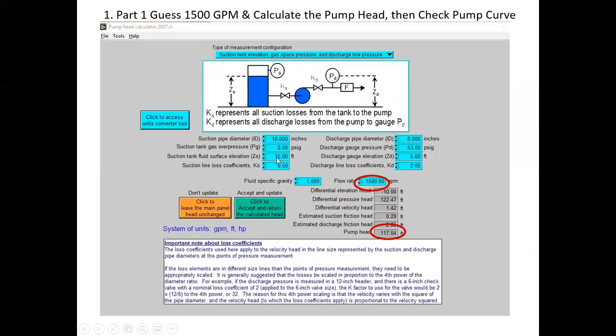That's well and good. The suction gas overpressure, nothing was given, so we assume the tank is open to atmosphere. So there is no gas overpressure. We just have atmospheric pressure sitting on top of the liquid surface. So that's 0 psig. The discharge gauge pressure was 53. I think that was given. The suction tank fluid surface elevation was given as 15 feet. And the discharge gauge was given as 5 feet.